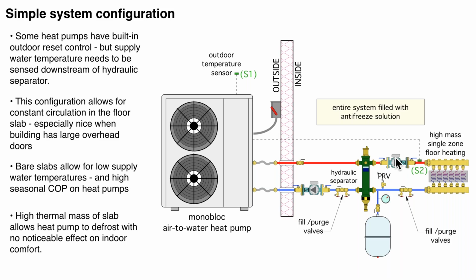And the nice thing about the hydraulic separator is this allows constant circulation on the right side. So we can keep this circulator running 24/7 during the heating season, and we're simply injecting heat. We're monitoring the temperature of the water going into the floor, and I'm showing this going directly back to the heat pump. Some heat pumps can do this.